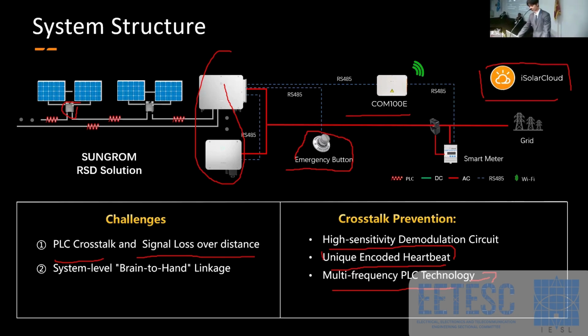Another thing about PLC crosstalk is incompatibility. So it's better to use a one-brand solution. If you choose Sungrow's inverter, it's better to use Sungrow's rapid shutdown. If you choose another brand, you had better choose their rapid shutdown, because it will make the system more reliable. As I said here, the rapid shutdown is not compatible. They do have their own unique ID or their own multi-frequency PLC technology. It's different. That's why different brand inverters and different brand rapid shutdowns cannot understand each other.